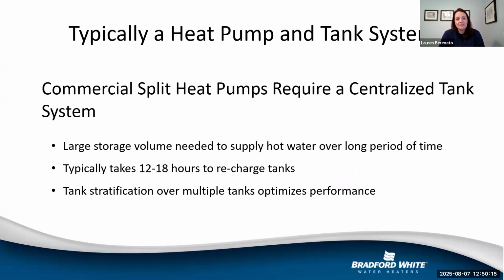Now, typically a heat pump and tank system is what we will see. So commercial split system heat pumps do require a central tank system. That is your storage tank that's needed for your heater to operate properly. Again, talking about time length of recharging, it can take around 12 to 18 hours. So when you think about an office building, when your office building is not being occupied, but when you think about a hotel or a dormitory, you don't necessarily have that time to fully recharge because those areas definitely require hot water accessible more often.